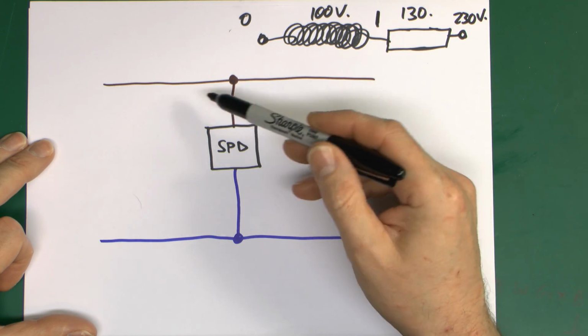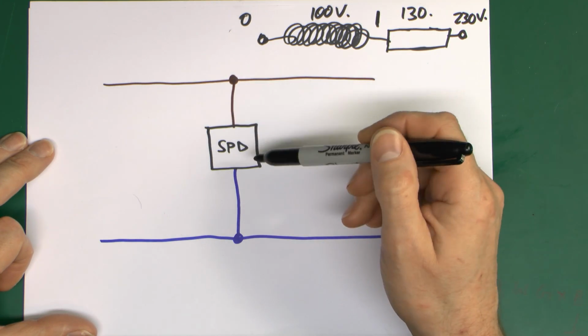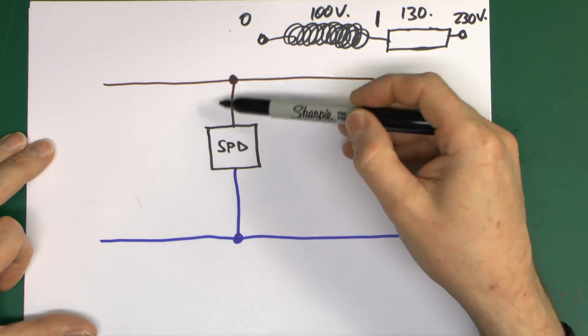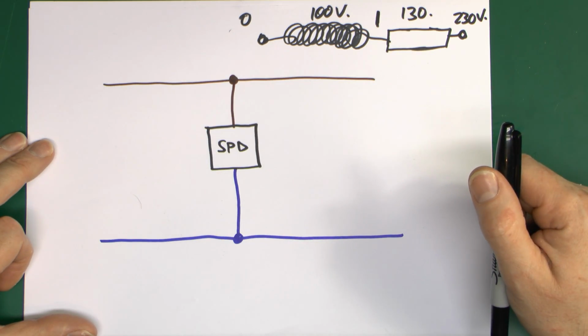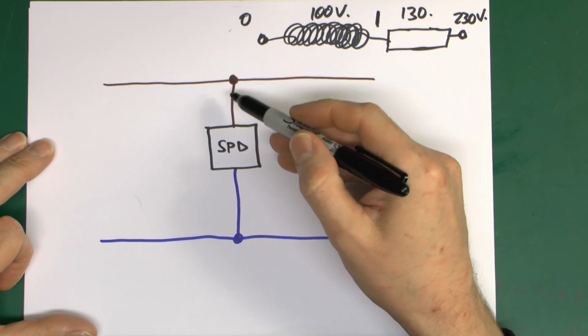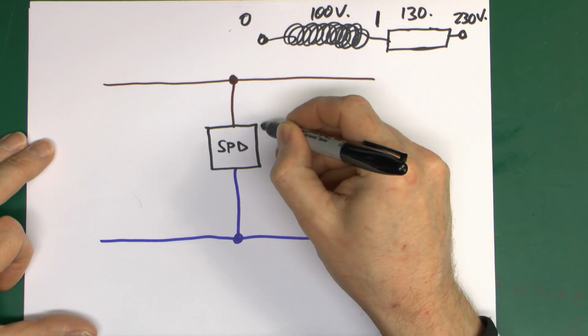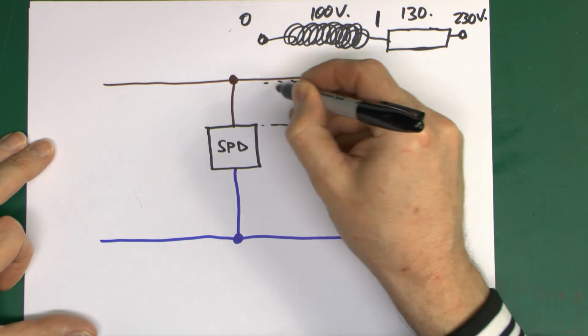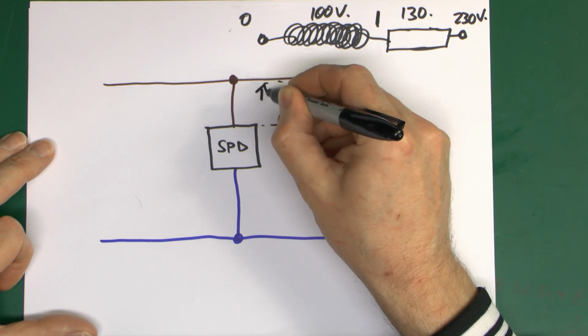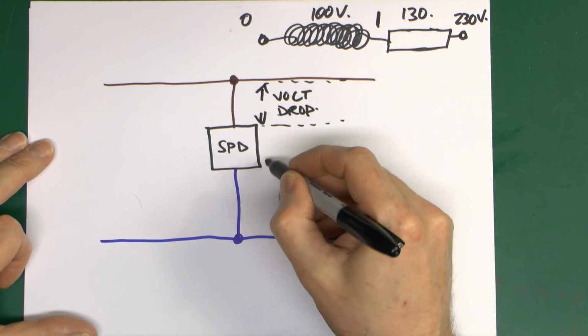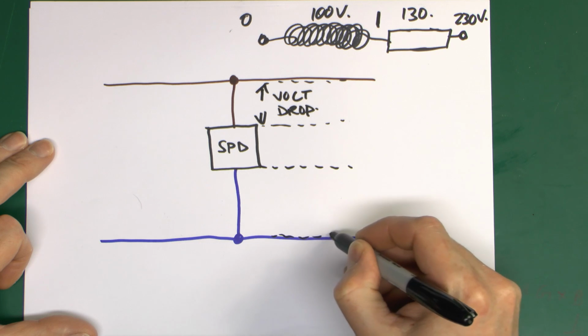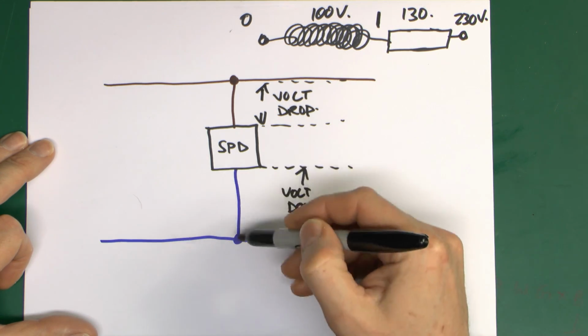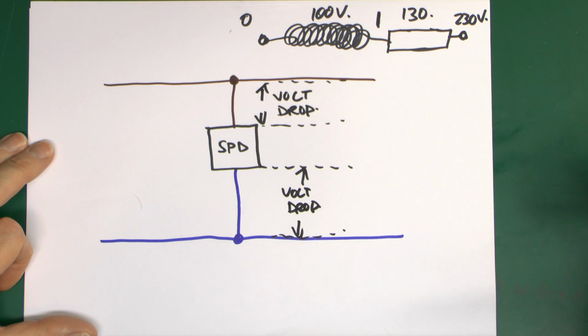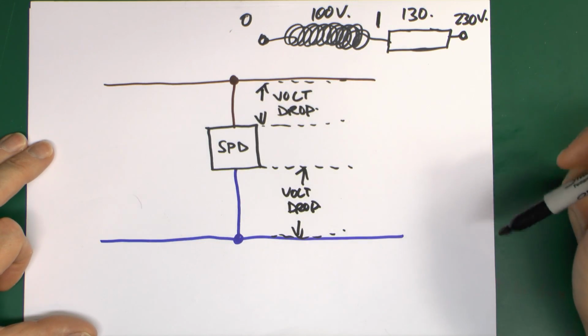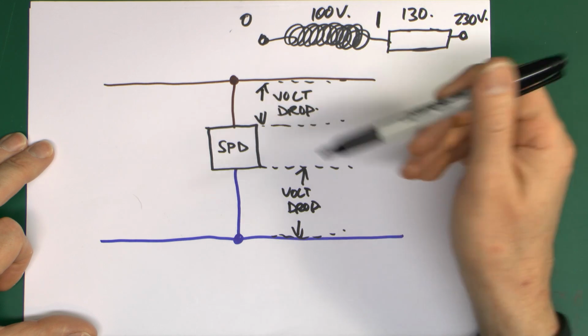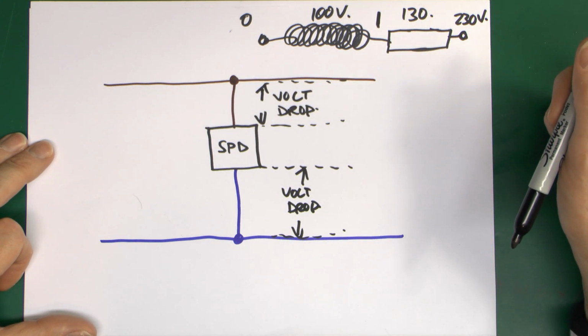And the other thing to consider here as well is that the current that flows when you've got a typical surge going on can be extremely large. And again, quite a large voltage across this, possibly many thousands of volts. So what effectively happens here is that the inductance of this wire, let me just draw this in here, actually ends up putting a voltage drop between these 2 points. And of course the same thing happens on the other conductor as well. So you get a voltage drop across the 2 pieces of wire. And for a fairly large surge, and say you had a metre of wire or something, this voltage drop can actually be something like 1,000 volts, or even more if you put extremely long wires in.